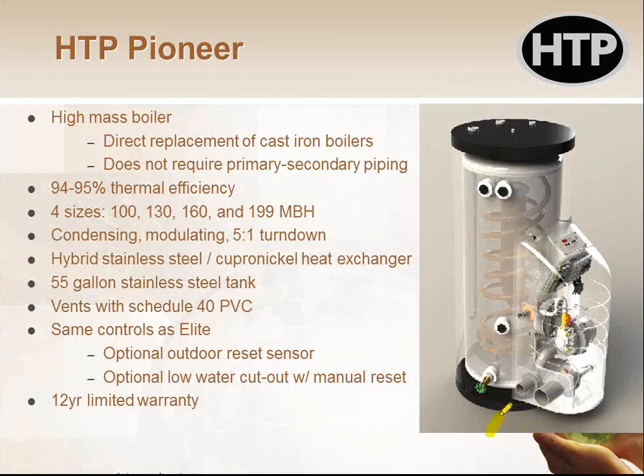So I've got my combustion air coming into this guy, right? I'm burning that through my high-efficiency burner. It's going up to this guy here, and then it's coiling down through all these loops, right? And then somewhere down here, boom, I let it go out and exhaust out my PVC vent out of the building. Right? So that's how that guy's looking. And then all the water is coming in here, filling up in the tank and going out.